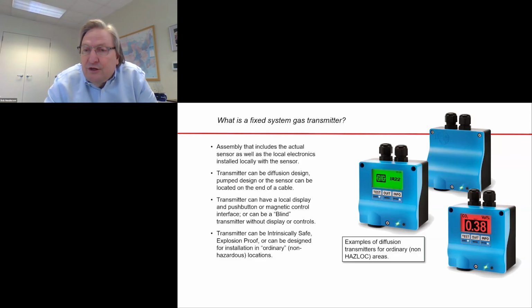But you have to figure out what certification is needed, and you don't want to go overboard if you don't have to. One of the most expensive aspects of acquisition for a fixed detection system is the wiring and conduit that you might be required to use to install the system.